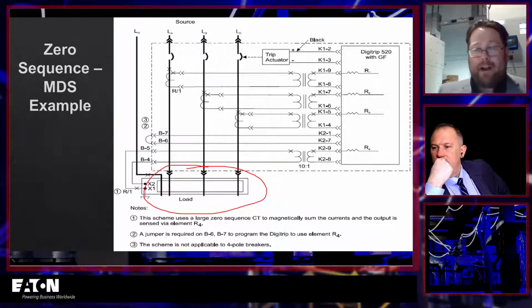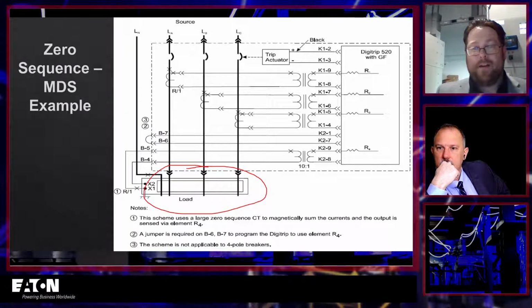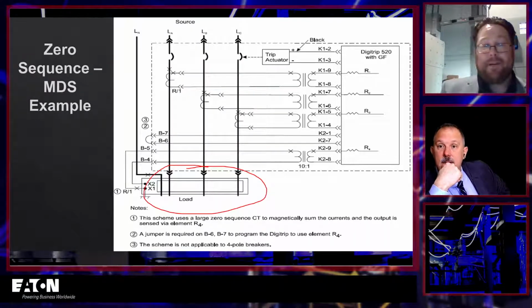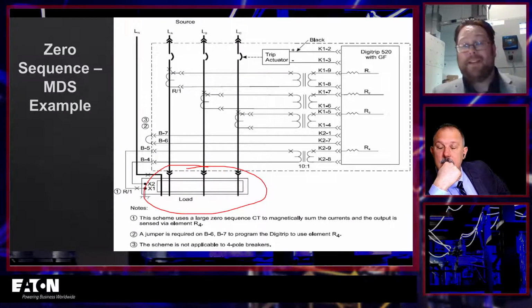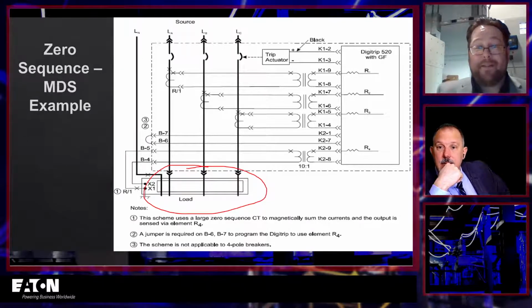the polarity doesn't matter; it's not as important. But with the zero sequence, think of it this way. I go to the back of the switchgear, and where does all the bus bar run? And especially now that we have all these service entrances that we like to put barriers up on, so you separate your line side from your load side, how do you know where that neutral bus really runs in the switchgear, where phase A, B, and C actually are bolted together? It's hard to trace out and follow the directions of everything. That's right. So we're still confirming again that all the connections work out to be the right direction.